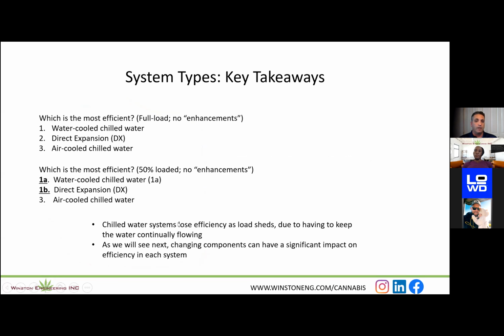When you're at full load, that means when you are at 100% of the load that you designed that equipment for, and no enhancements, we'll get into the enhancements later. That's more or less just improving the components' efficiency. Just generally speaking, you're going to be looking at water-cooled chill water being the most efficient out of these. Direct expansion, in many cases, will be the second, and air-cooled chill water, in many cases, will be the last.